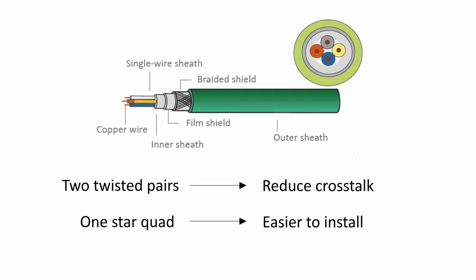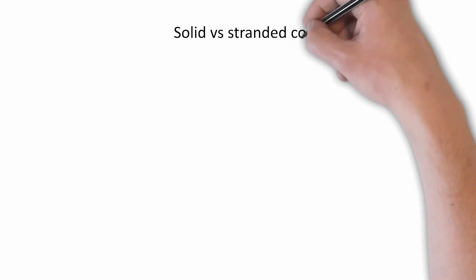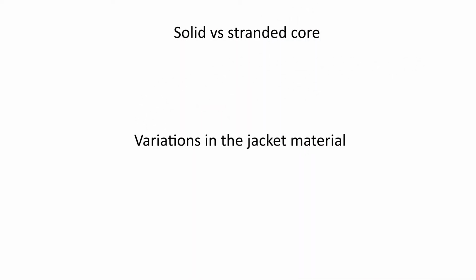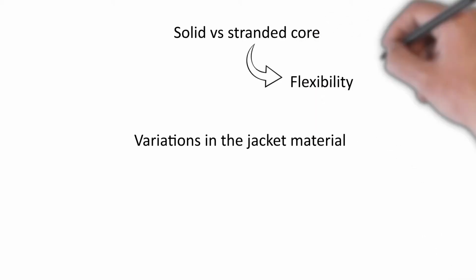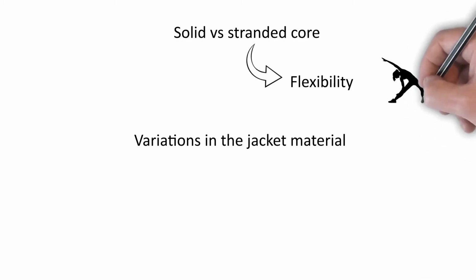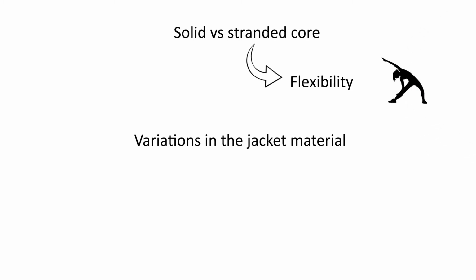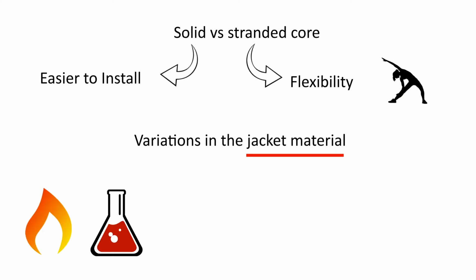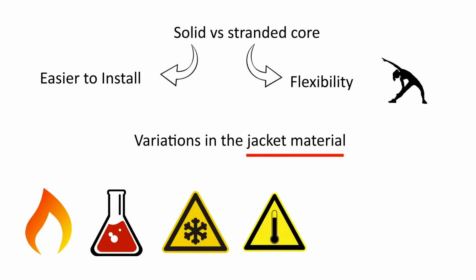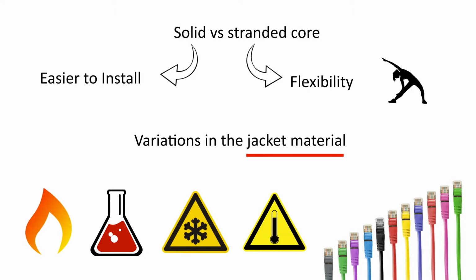The structure of the wires in copper cables can vary. They can have a solid core or stranded core, and variations in the jacket material and construction. Stranded core wires, for example, are more flexible. They are suitable for indoor applications where twisting and bending can occur. Solid core cables, meanwhile, are easier to install. Different jacketing materials can provide resistance to flames, chemicals, or extreme temperatures, or in specific applications, come in different colors.